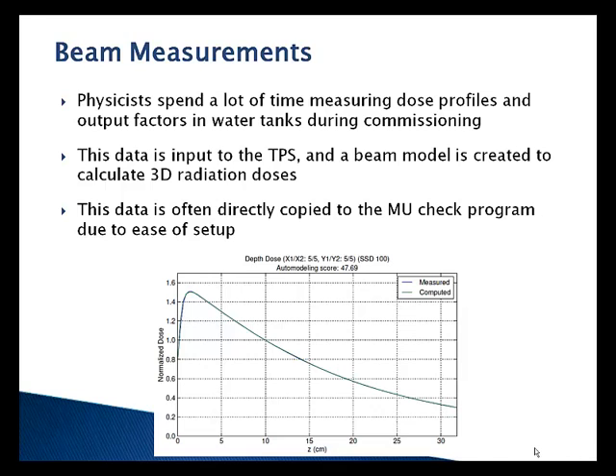So I'm a physicist, and we spend a lot of time measuring dose profiles and output factors in water tanks during commissioning. We then input all that data to our planning system, and a beam model, like Nico's talked about, is created to calculate the 3D radiation dose. Data is often directly copied to the MU check program due to ease of setup. And the rest of this talk is going to be about all the steps along the process and where to look for errors and how errors can accidentally get propagated. So we're going to really hit on a lot of these things. So the first thing I did is I measured one set of data. I copied that to my MU check system, which I expect to check my planning system.